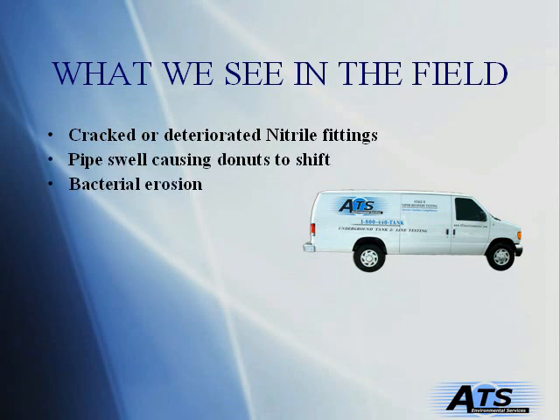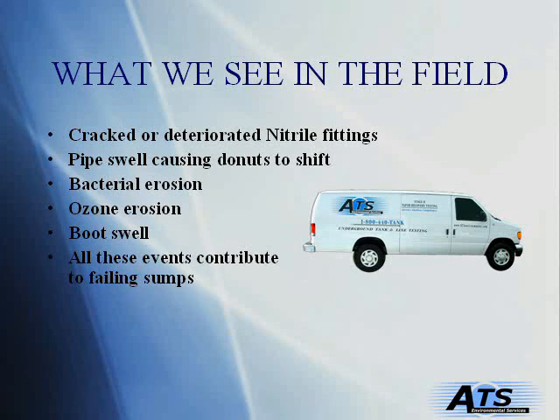Here are examples of some of the problems that we see in the field every day. Chances are you've seen these at some of your sites as well. Cracked or deteriorated nitrile fittings, pipe swell causing the donuts to shift, bacterial erosion, ozone erosion, boot swell. All of these events contribute to failing sumps.